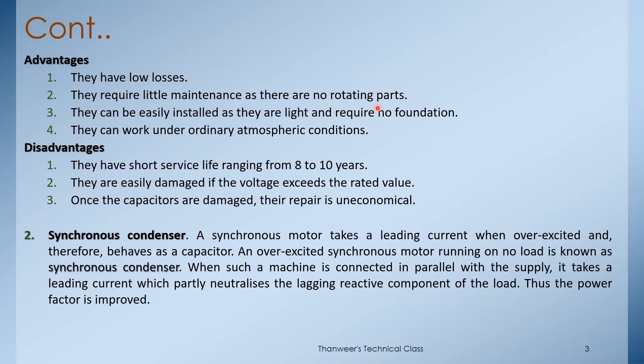Advantages of static capacitors: they have low losses, require little maintenance as there are no rotating parts, can be easily installed as they are light and require no foundation, and can work under ordinary atmospheric conditions. Disadvantages: they have a short service life of 8 to 10 years, are easily damaged if the voltage exceeds the rated value, and once damaged, repair is uneconomical.